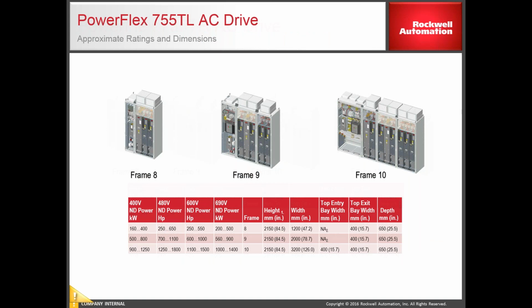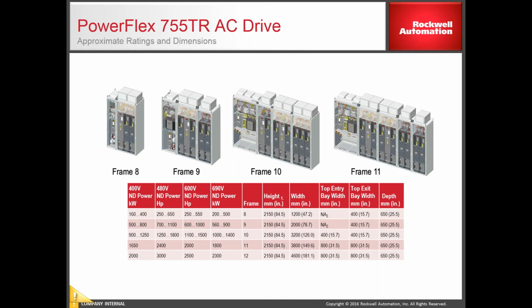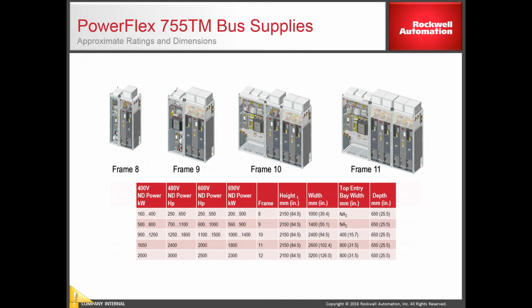So again, kind of the same concept. Frame 8 at 480 volts, we can go up to 650 horsepower. Frame 9 we can get up to 1100, and a frame 10 we can get up to 1800 with the TL drive. So again, we just parallel those power structures to get the increased horsepower. The 755TR, again, we can go up to 3,000 horsepower, again, by paralleling the power structures. And then the TM, again, we go up to 3,000 horsepower on this first release.